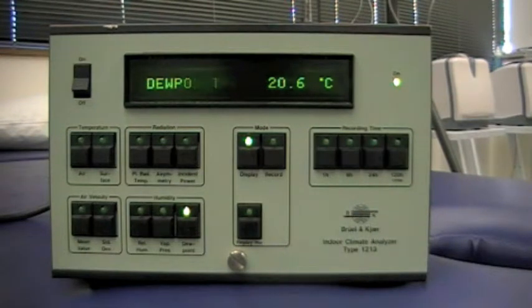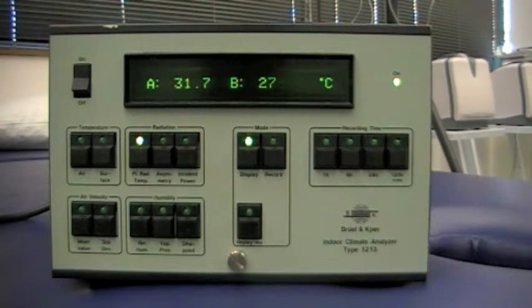This is displaying the radiant temperature. You've got two readings there, A and B. A is the temperature that's pointing towards the hot surface of the window where the sun shines there. And that's recording a higher temperature than the B surface which is pointing into the room. And you'll see that the B temperature is in fact close to the air temperature that we looked at a few moments ago.